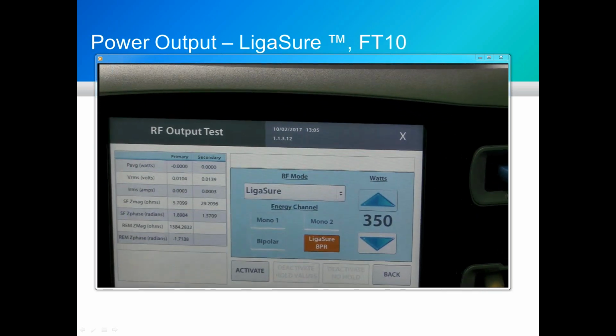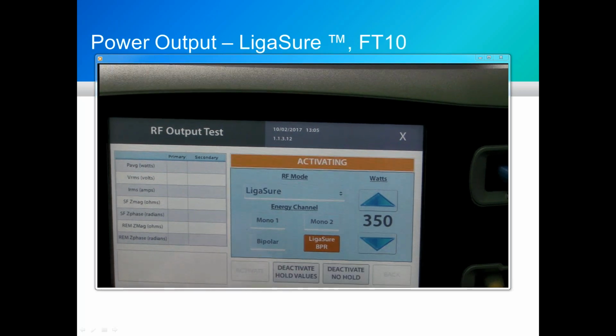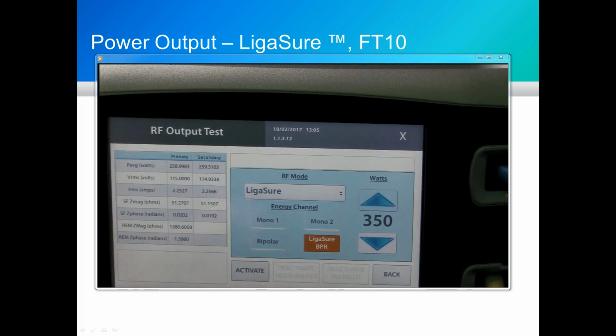So if you watch the table on the left-hand side of the screen there, you'll see IRMS, VRMS, P average. Again, that's being picked up in 2 different points within the FT10 itself. But if you look especially at SFZ mag, that is the resistance or the impedance now that the generator thinks it sees as it looks out at the load resistance of your analyzer. And again, the DC resistance, the capacitance, and inductance all come into play.